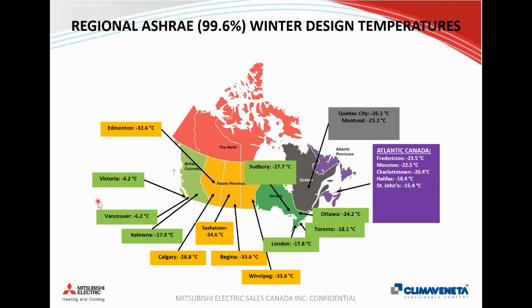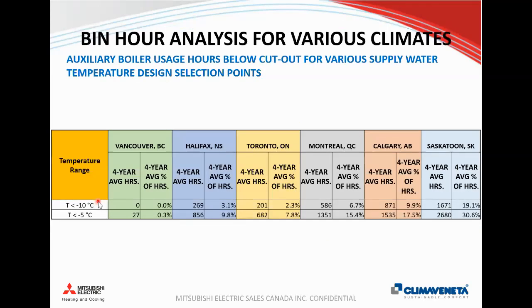So we do have a diverse climate, but what I did want to show is just breaking down the similar weather data for Toronto. So this is kind of sorted from best case to worst case. If we say, okay, well, a 45-degree Celsius supply temperature down to -10 is suitable for your buildings, just looking at even Montreal, they spend about 300 more hours than Toronto does. So there's still good usability of the heat pump that we can get.